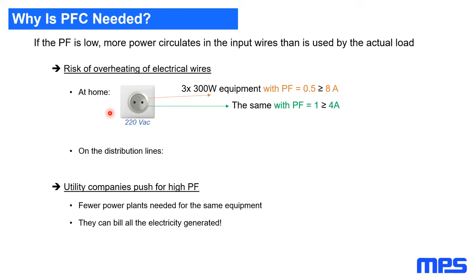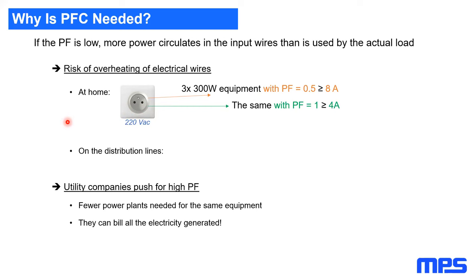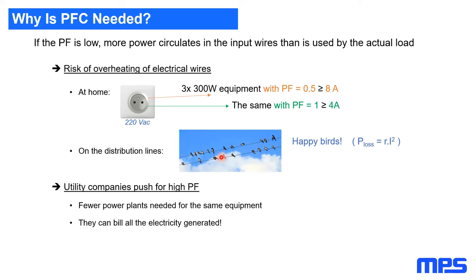Looking at it from a higher level — the distribution lines bringing electricity to your neighborhood — more current in the wires means more losses. The losses are proportional to the square of the current. If you double the current due to a power factor of one half, you quadruple the losses in the wires. In general, it's not good to have a higher current than necessary circulating in the wires.